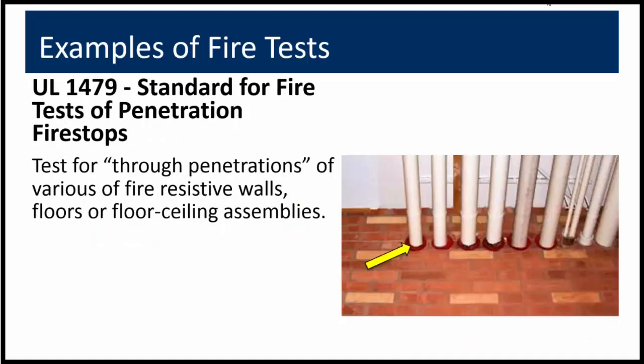This is an area where we receive a large number of project inquiries. It's important to know that the rating of the roof covering is entirely different from the structural fire resistance rating of the roof assembly intended to withstand a fire from within the building. UL1479 covers through penetrations of various materials and construction that are intended for use for openings in walls, floors, and floor ceiling assemblies. This typically involves products known as fire caulks. There are literally dozens and dozens of fire tests which apply to building construction, and it's important that the appropriate test be used for the application.